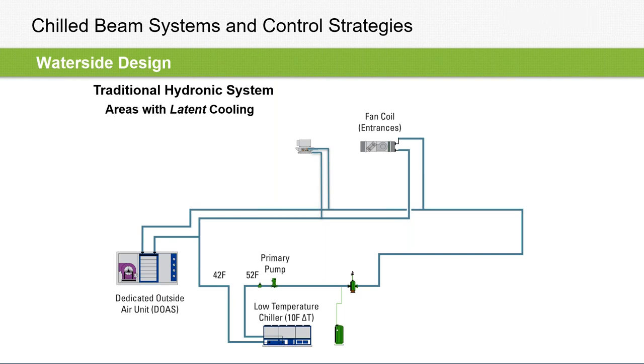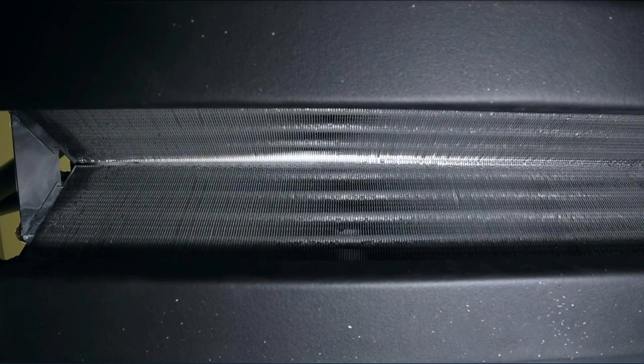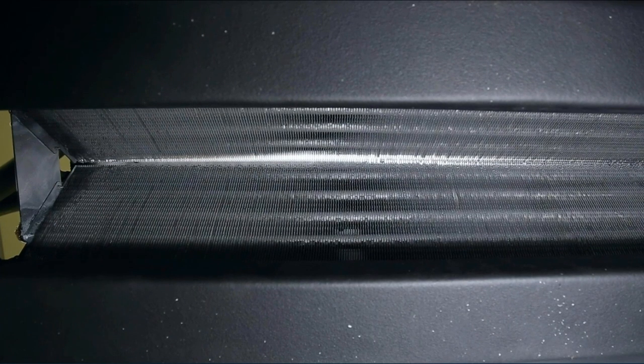And essentially what you have to do to make this work and not rain is to add a drain pan to the chilled beam. So you can imagine with a standard ACBL flat water coil, if you put a drain pan below it, you're blocking all that induction free area. So what we've done is actually this black rectangle on the bottom of this coil is our drain pan, and we actually broke the flat water coil into an A-frame. So it actually ends up with more surface area. So even at the tempered water conditions, you'll get more capacity per foot of beam, but it also allows us to capture that water if it does condense.